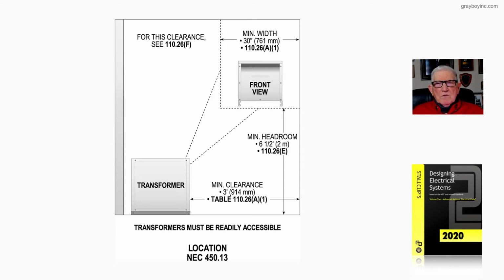So you do have to remove the covers you see in the front view there, and infrared the windings to see there's no hot spots and so forth. And then also you're required to clean it out and vacuum it and so forth in accordance with the Annex L, which will give you the section numbers, and NFPA 70B as in boy, the maintenance standard.